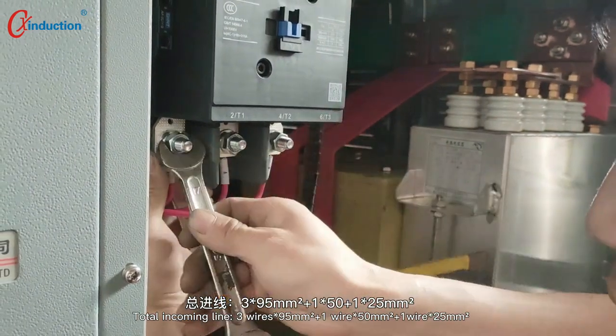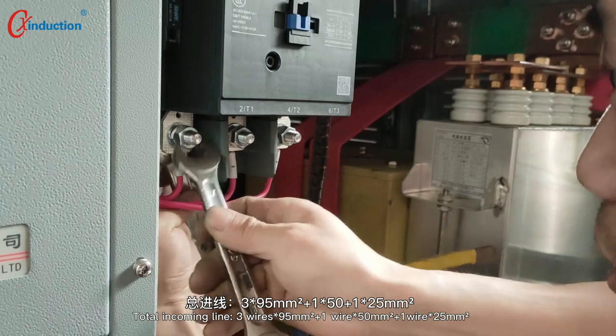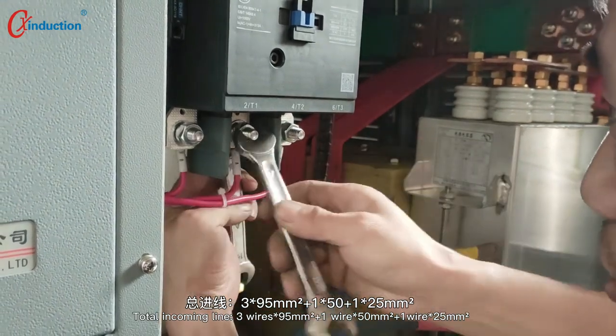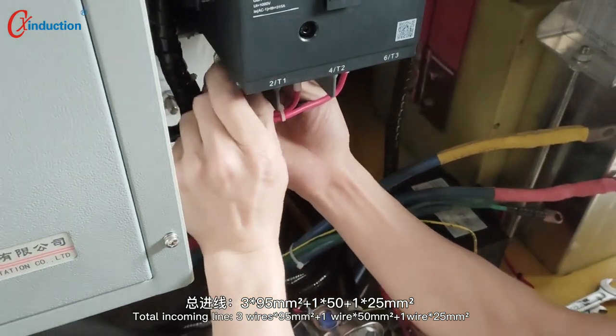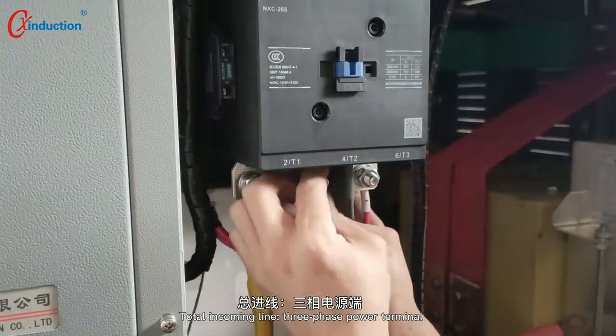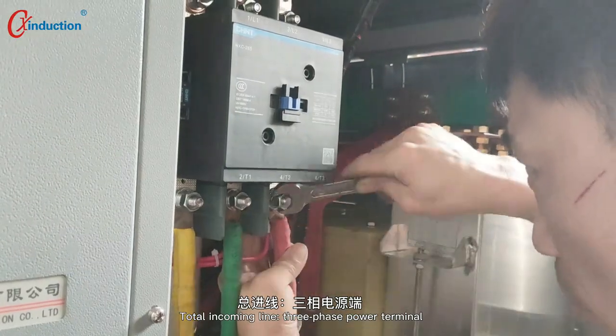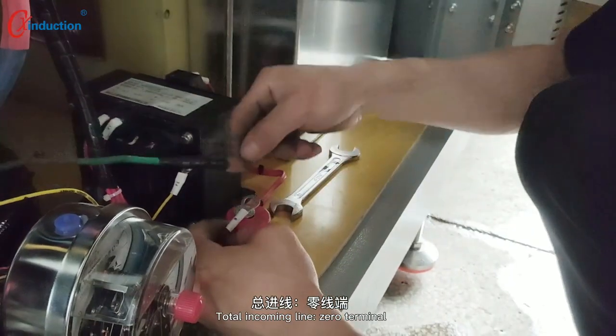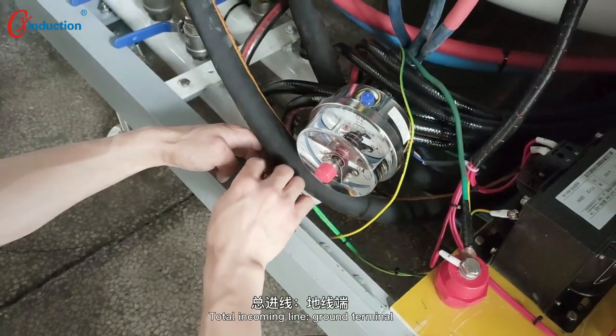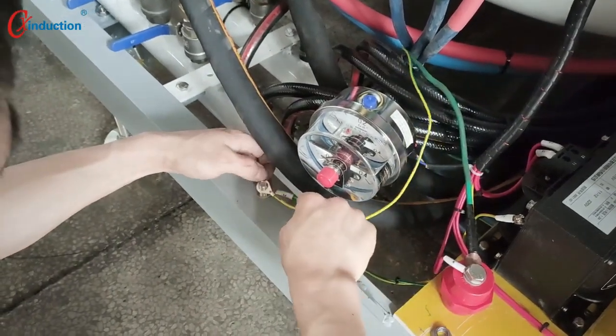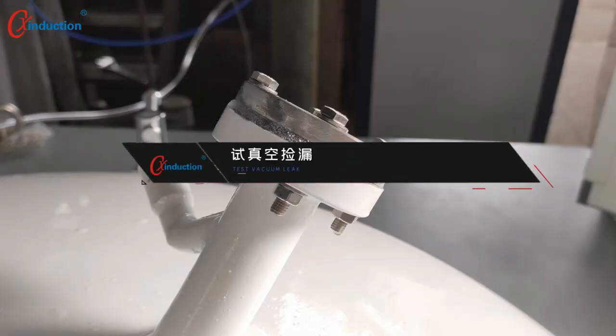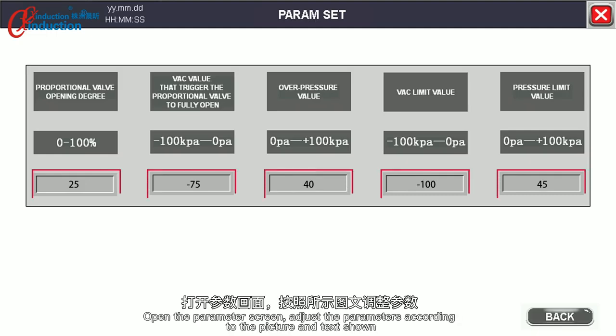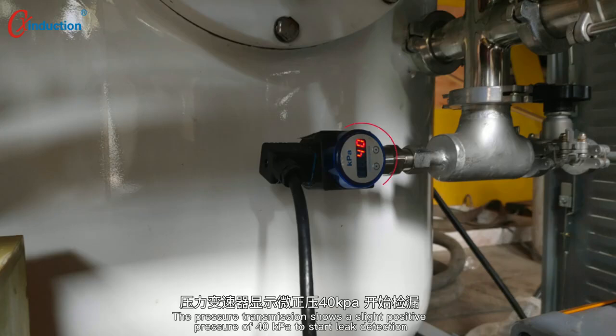Total incoming: 3 wires with 95 square millimeter, 1 wire with 50 square millimeter and 1 wire with 25 square millimeter. Total incoming 3-phase power terminal. Total incoming N terminal. Total incoming ground terminal. Open the parameter screen, adjust the parameters according to the picture and text shown. The pressure transmitter shows a slight positive pressure of 40 kPa to start leak detection.